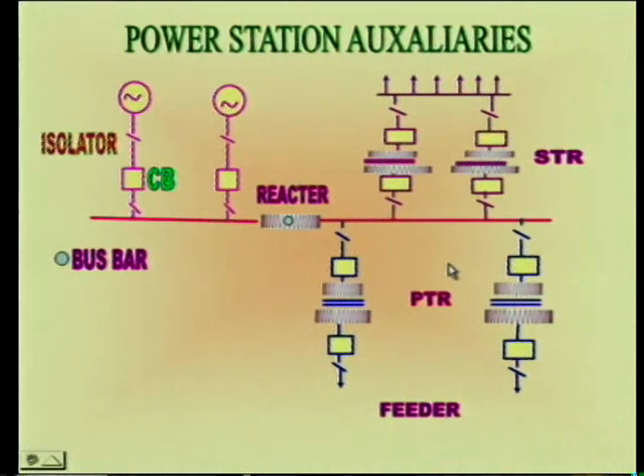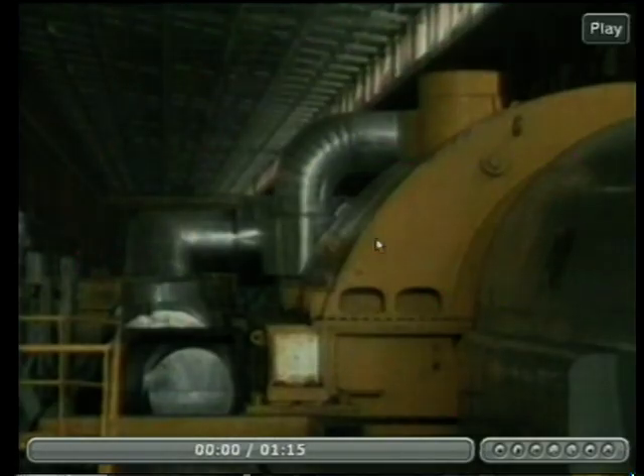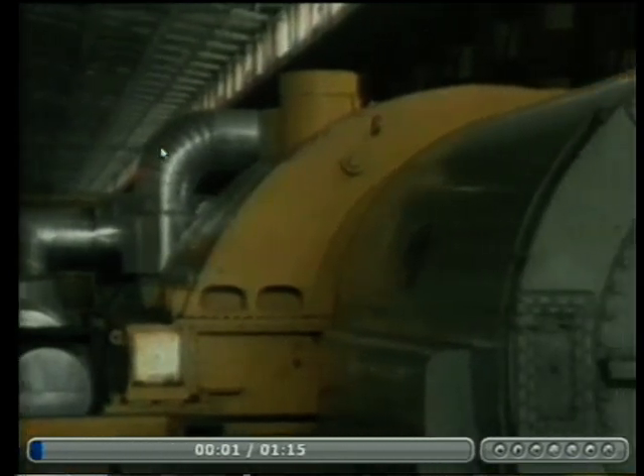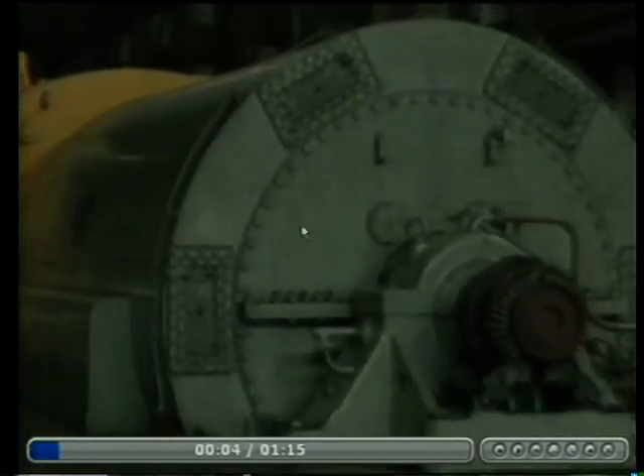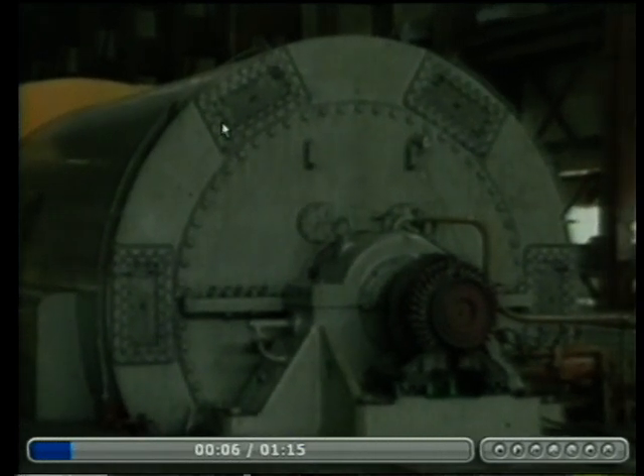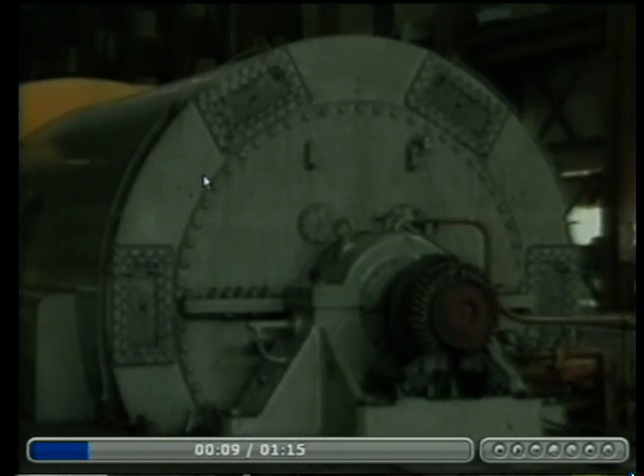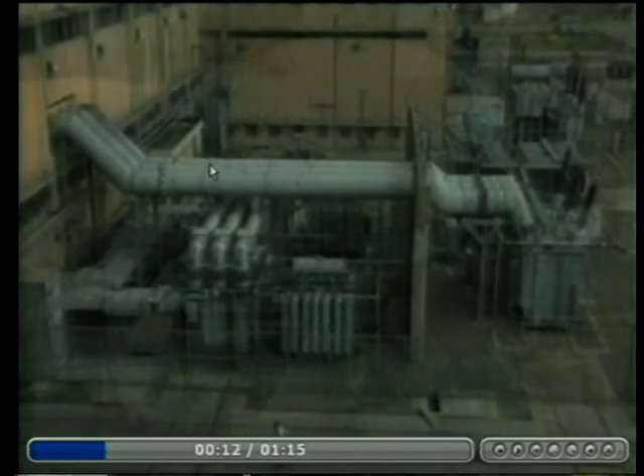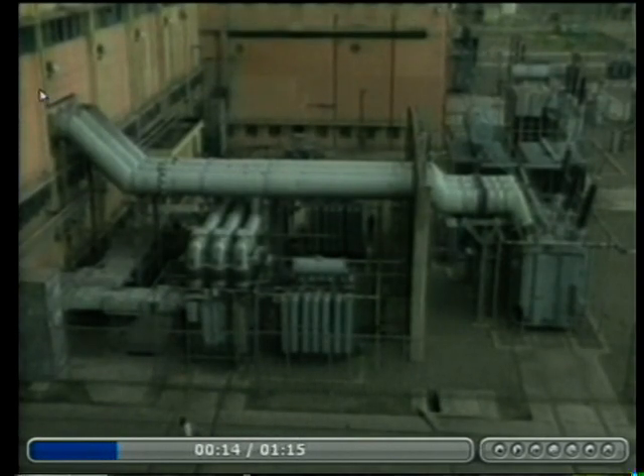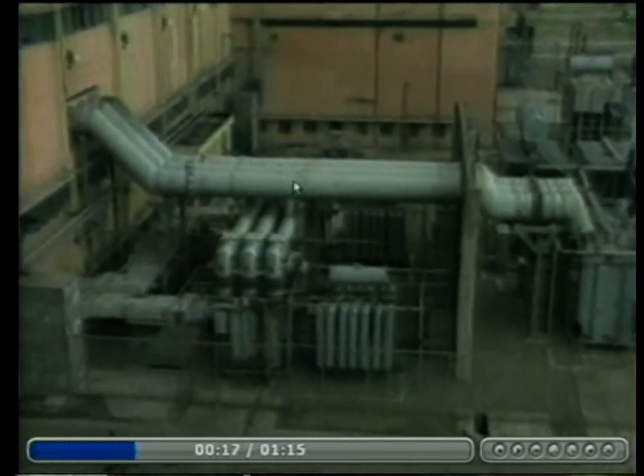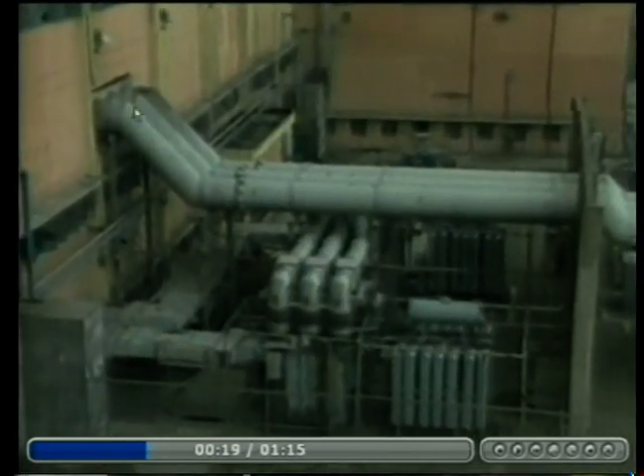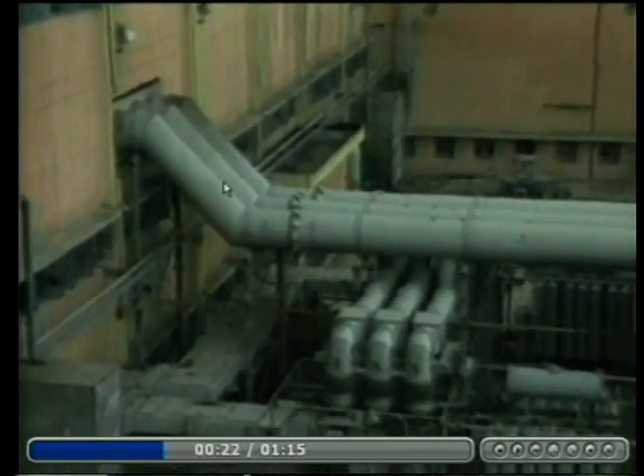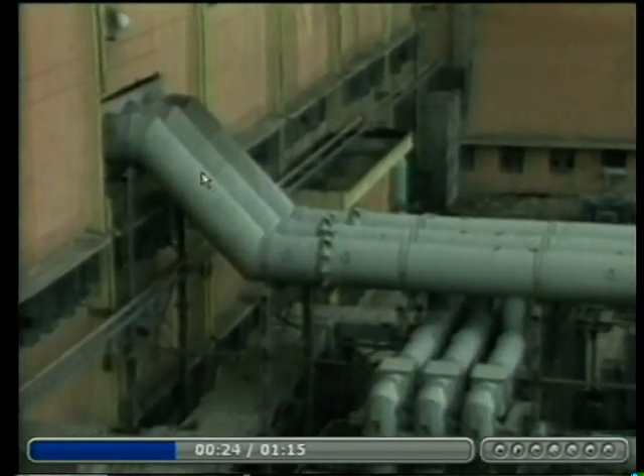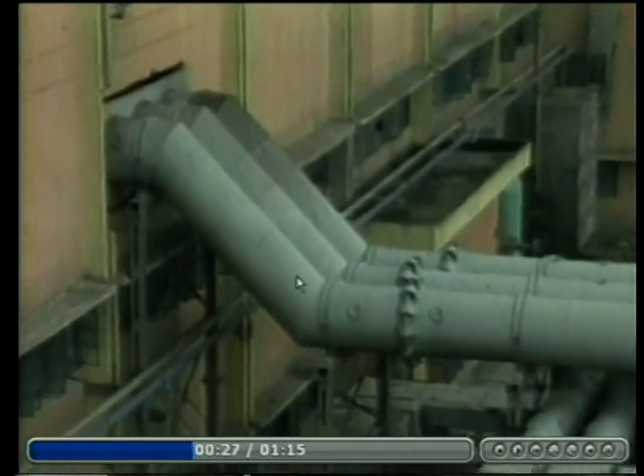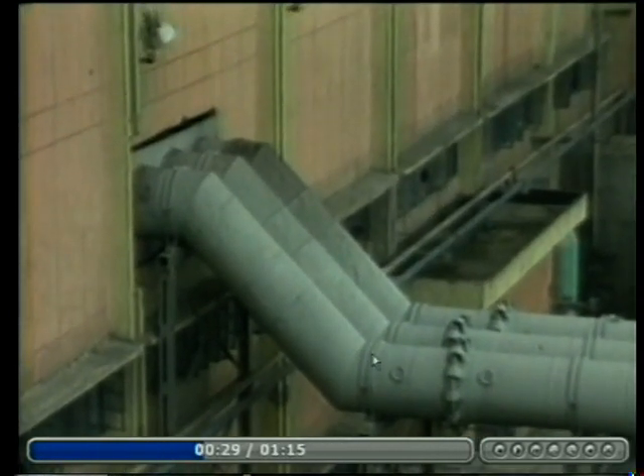Now, you can see here a clip for you. This is a thermal power station. You can imagine how big this generator is. The generator generates low voltage and the voltage is passed to the power transformer, carried by 3 bus bars. You can see the size of the bus bars because the voltage is low and the current is very high, and these are the 3 bus bars.